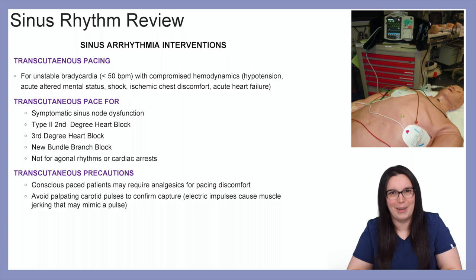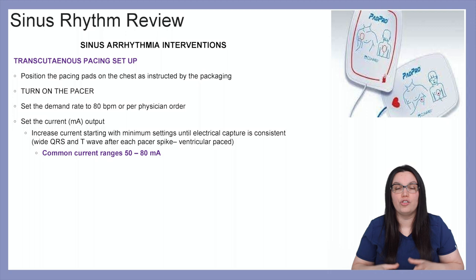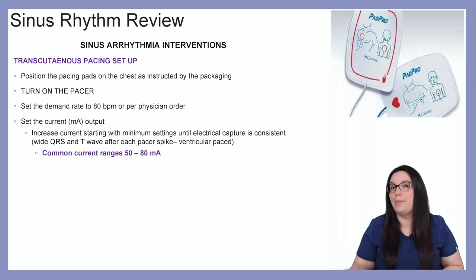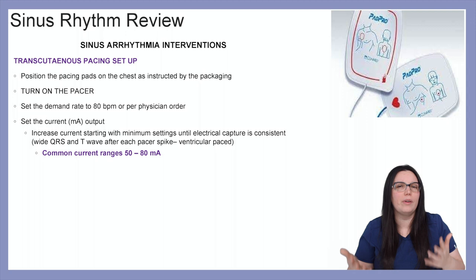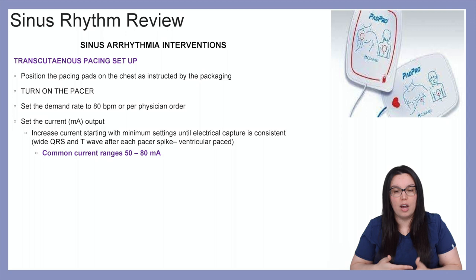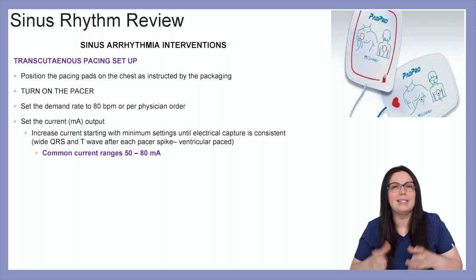To set up transcutaneous pacing, position the pacing pads on the patient as instructed by the packaging — normally one pad goes over the right anterior chest wall and the left pad goes on the left midaxillary line next to the heart. Turn on the pacer first, and set the demand rate to 80 beats per minute or whatever the physician instructs. Set and increase the current mA output starting with a minimum setting, moving up until electrical capture is consistent — which would be a wide QRS and a T wave after each pacer spike. Common current range is between 50 to 80 mAs.